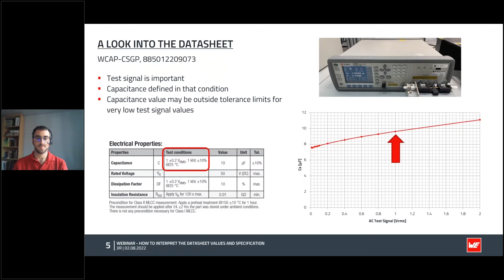I want to show you something else about this. On the right, you can see some examples of the measurements we offer in Red Expert. This is the same capacitance variation for different test signals. The LCR meters have some output impedance in the path of the test signal, for example 100 ohm, which means that the capacitor will only see part of the test signal that we set. For this reason, some LCR meters have some kind of level control functionality.